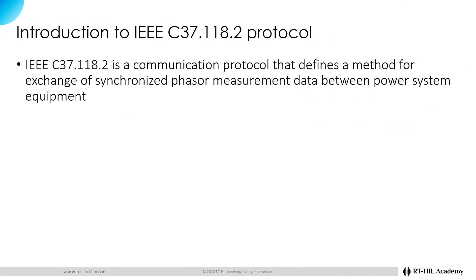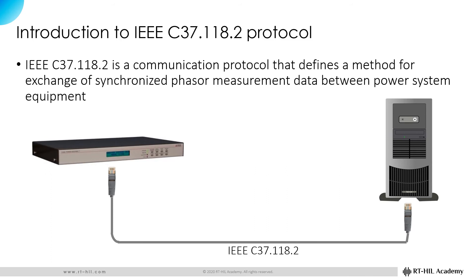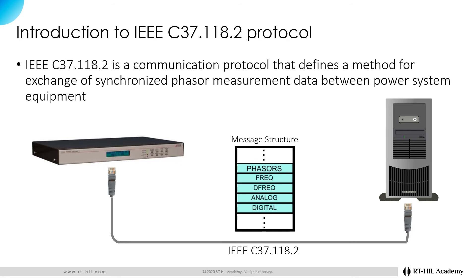What is the IEEE C37.118.2 protocol? The IEEE C37.118.2 is a communication protocol that defines a method for exchange of synchrophasor measurement data between power system equipment. In other words, this protocol is the language by which the phasor measurement units, or PMUs, communicate with other devices. Each data message complying with the IEEE C37.118.2 protocol contains the information of the synchrophasors, system frequency, rate of change of frequency, and user-defined analog and digital values. The PMU has to be configured to select what synchrophasors and what analog and digital values to include in the data messages.